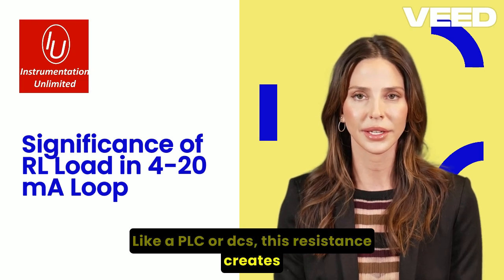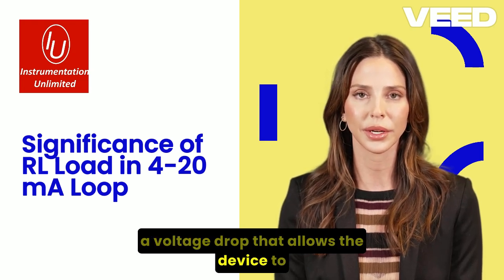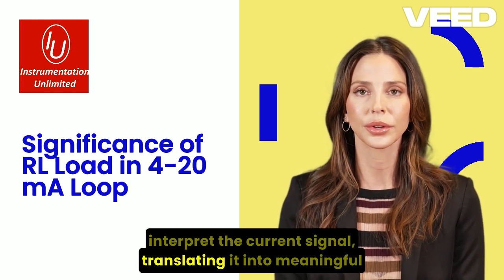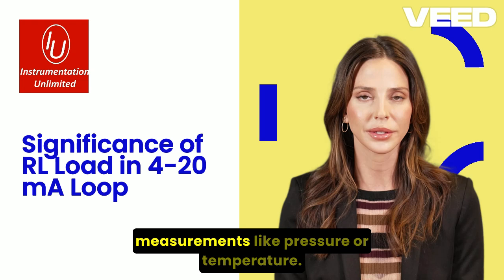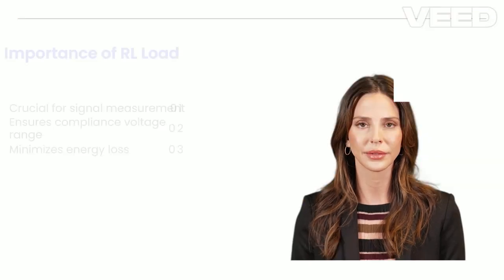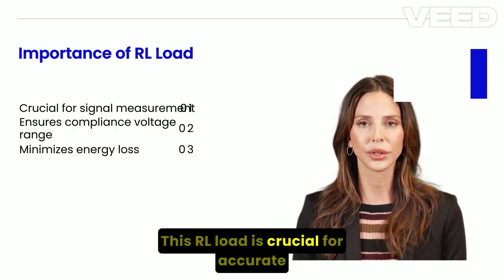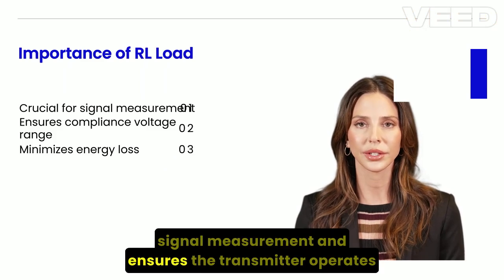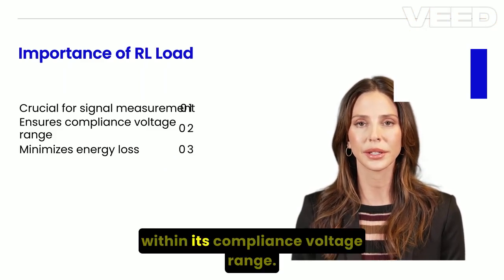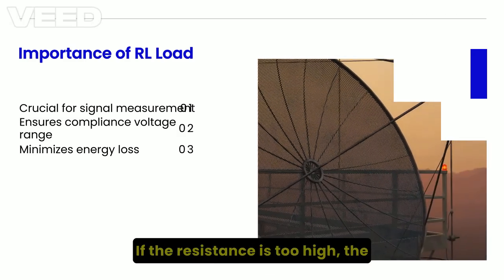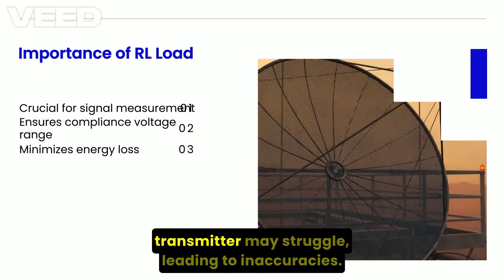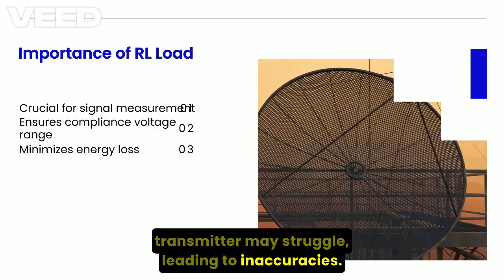This resistance creates a voltage drop that allows the device to interpret the current signal, translating it into meaningful measurements like pressure or temperature. This RL load is crucial for accurate signal measurement and ensures the transmitter operates within its compliance voltage range. If the resistance is too high, the transmitter may struggle, leading to inaccuracies.